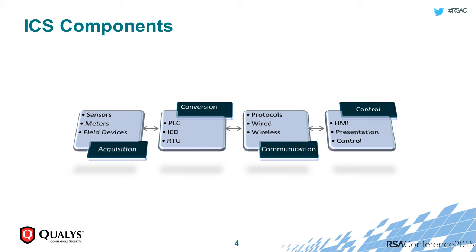By acquisition, I mean sensors, meters, field devices — devices that typically gather data like temperature and pressure. Conversion components include PLCs, IEDs, and RTUs, which carry this data through various communication channels to the SCADA master or HMI.